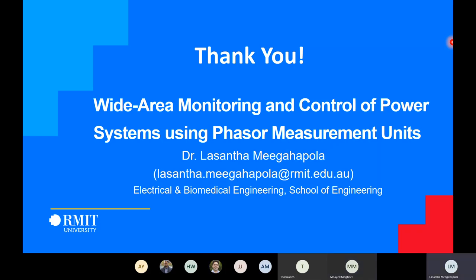And one point on future research direction: even now, things are coming to the distribution side as well. On the distribution side, the phase angles are pretty much small, so that means you have to have high accuracy as well. Therefore, some US researchers at Berkeley in California developed a technology called microsynchrophasors. The term microsynchrophasor means they can capture very, very accurate phase angle differences at the distribution network level. So that is an emerging area of research.